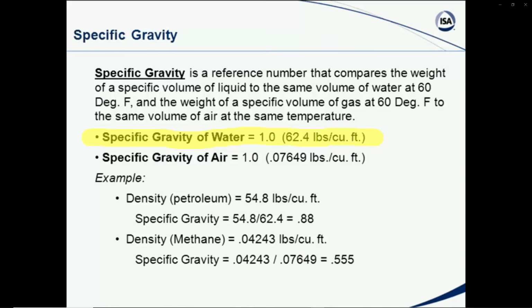So if you have something that weighs more than 62.4 pounds per cubic foot, the specific gravity will be greater than 1. If you have something that weighs less or has a lesser density, then the specific gravity will be less than 1. For example, let's say that we have a petroleum product, 54.8 pounds per cubic foot, and we're given that on the exam or on a test, and we don't know what the specific gravity is. How do we get that? We divide that number by 62.4. In this case, the specific gravity would be 0.88. Many times they will give you the specific gravity. Sometimes you may have to look up the specific gravity. So you need to have some tables, charts that do have some specific gravities. Or if you can find the density or the specific weight, pounds per cubic foot, of that particular liquid, then you can divide by 62.4.